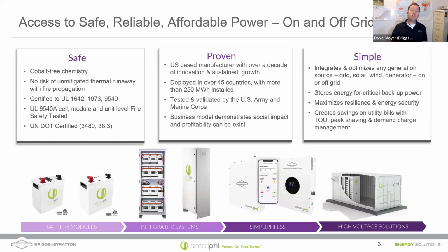I'm seeing a lot of opportunities and market drivers with these energy storage systems. Many people around the country are now being hit with time-of-use rates, where energy is more expensive at certain times of day—utilities finding creative ways to charge us more. We can tell an energy storage system that energy is more expensive during certain times, and it can discharge itself to cover your loads and help you avoid buying that expensive power. Demand charges are also becoming more common on the commercial side.